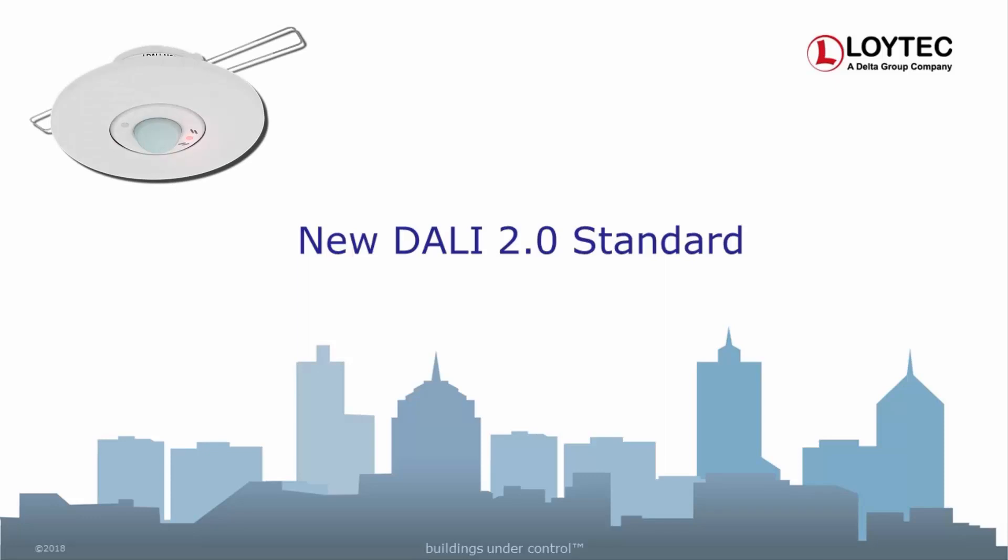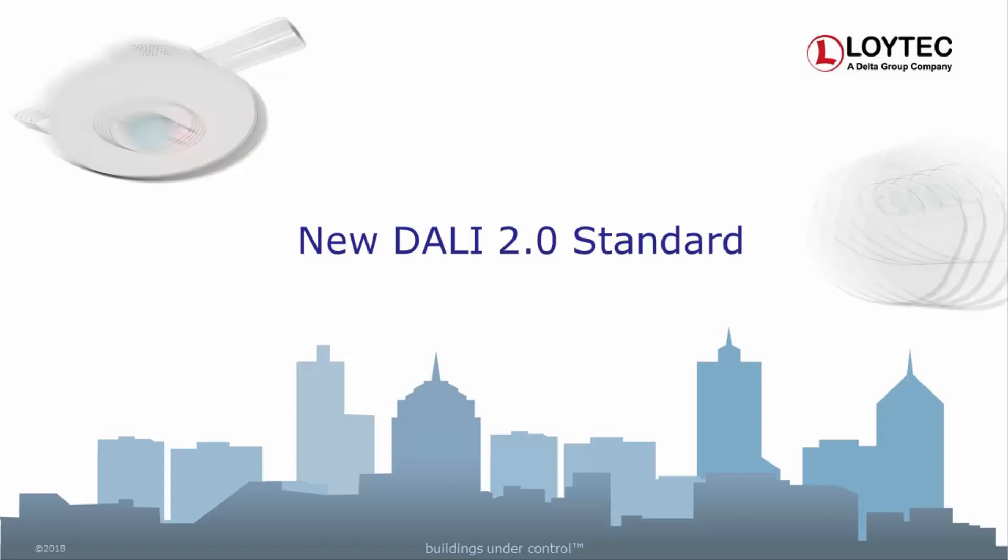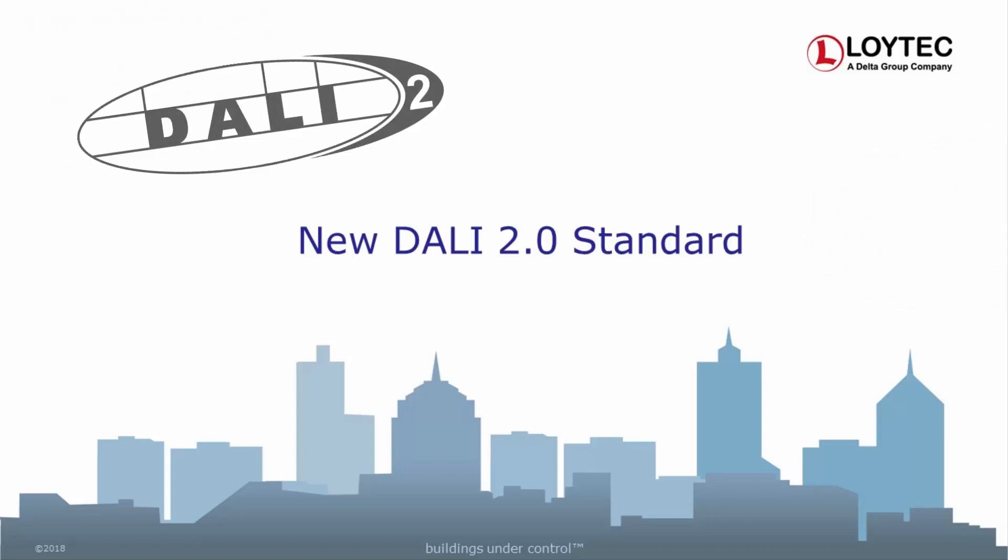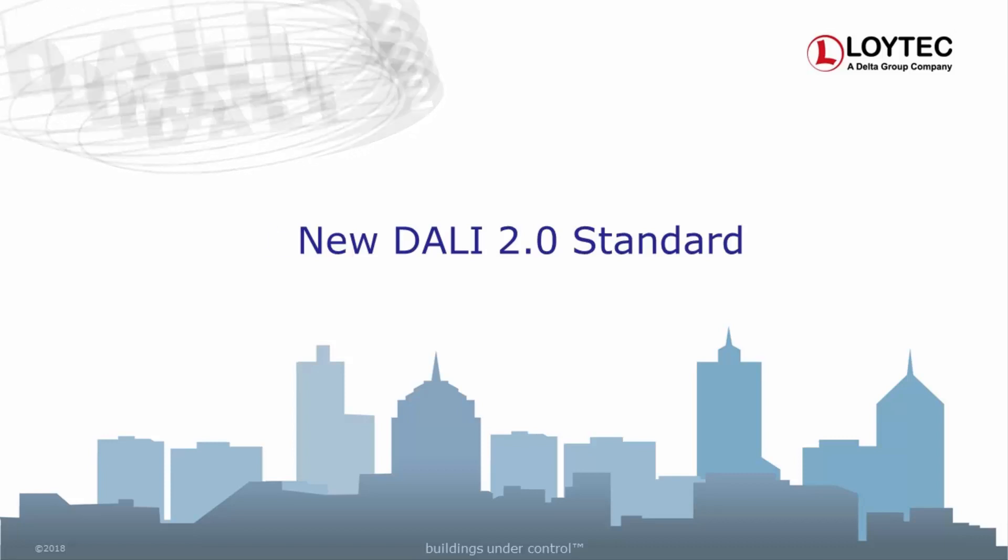Prior to DALI 2, sensors and buttons were not covered by the DALI standard. Therefore, proprietary extensions of the DALI protocol were needed in order to connect this type of devices to the DALI network. With DALI 2, those type of devices are standardized in the IEC 62386-103. The LDALI now supports the DALI 2 standard and allows to use all buttons and sensors that are implementing version 2 of the DALI standard.